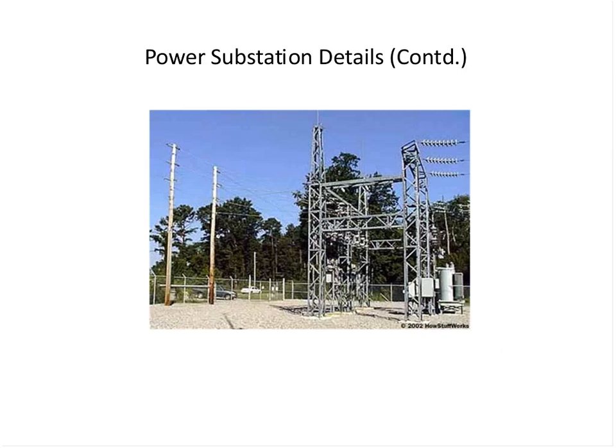Now let's go further, and we get to the distribution bus where the voltage regulators are. To the right of this, as you can see, the distribution lines are now connected to this distribution bus, and you see the two towers on the left side with cables running in opposite directions. The cables in between the poles are just meant for support. And then you have left and right cables that actually carry the electricity out onto the distribution network. Now we are in the thousands of volts going out of here, as opposed to hundreds of thousands of volts.